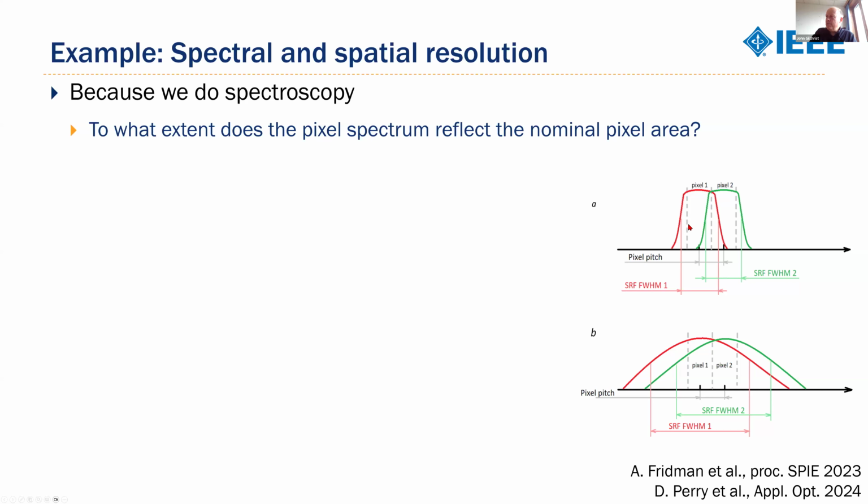We can define a peak width, and we know the spectral range or the width of the field of view, and we can just take the field of view, divide by the peak width, and that will be our equivalent number of pixels or effective pixel count. So I think we call it equivalent actually. So this is now a much more realistic number for the number of pixels or bands that you actually resolve, even though resolution is still undefinable.